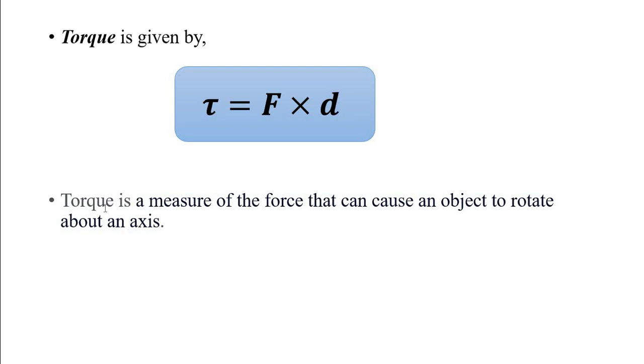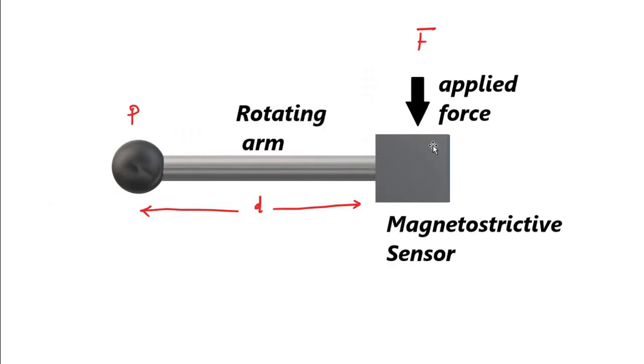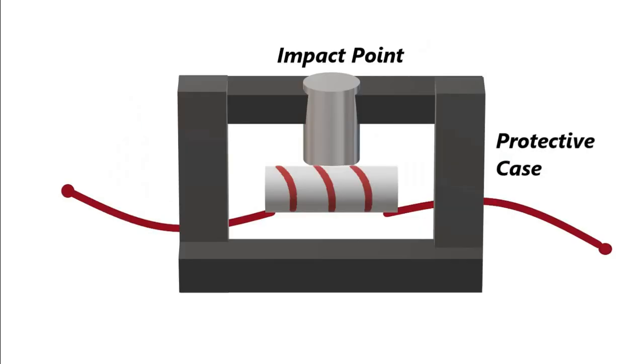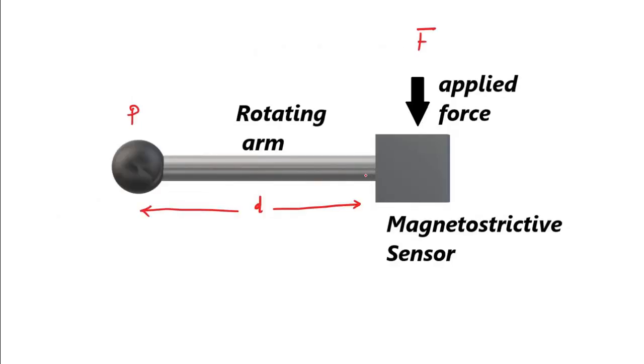Torque, as we know, is the rotating power of a force — it can cause an object to rotate about a certain axis. Torque is given by force times perpendicular distance. This design consideration is used: the magnetostrictive setup with the solenoid or toroid is kept, through some kind of lever or connecting rod arrangement, free to rotate at a certain fixed distance D from the point where we want to measure torque.